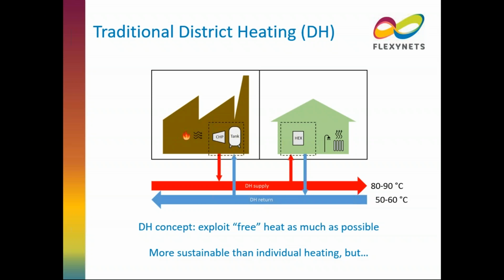However, it also includes some drawbacks. It's typically performed at a relatively high temperature, with a supply temperature of 80-90 degrees and return temperature of about 50-60 degrees, so a temperature difference between supply and return of 30-40 degrees. With these distribution temperatures, thermal losses are not negligible. Moreover, the fact that the temperature is so high prevents the possibility of integrating some available heat sources found within the urban context.